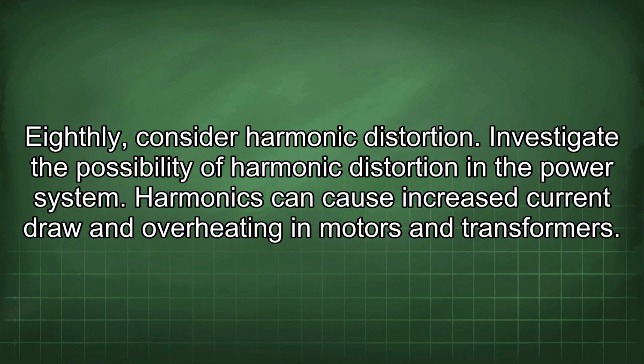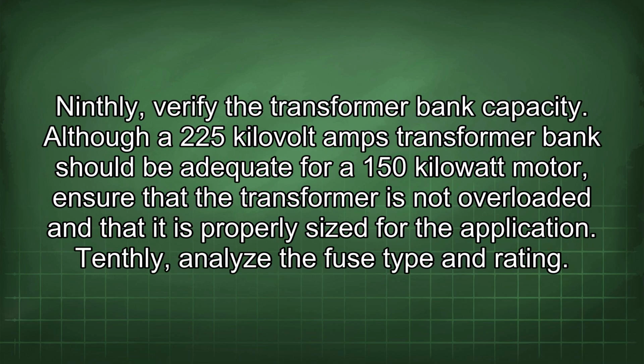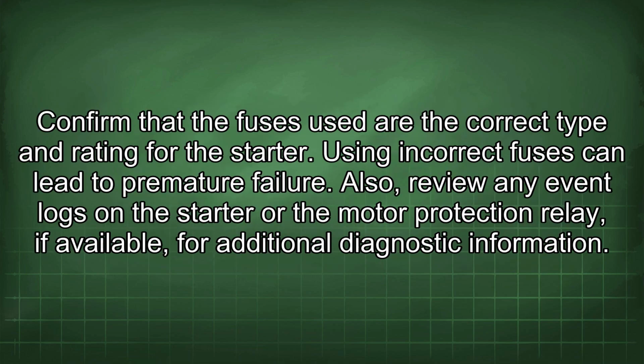Eighthly, consider harmonic distortion. Investigate the possibility of harmonic distortion in the power system. Harmonics can cause increased current draw and overheating in motors and transformers. Ninthly, verify the transformer bank capacity. Although a 225 kVA transformer bank should be adequate for a 150 kW motor, ensure that the transformer is not overloaded and that it is properly sized for the application. Tenthly, analyze the fuse type and rating. Confirm that the fuses used are the correct type and rating for the starter. Using incorrect fuses can lead to premature failure.